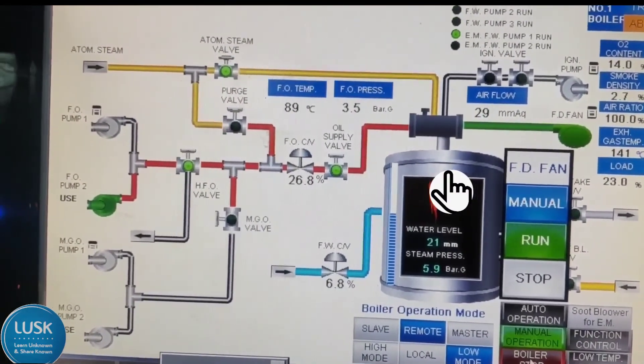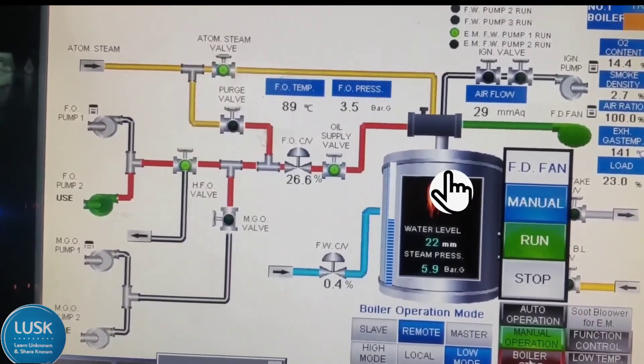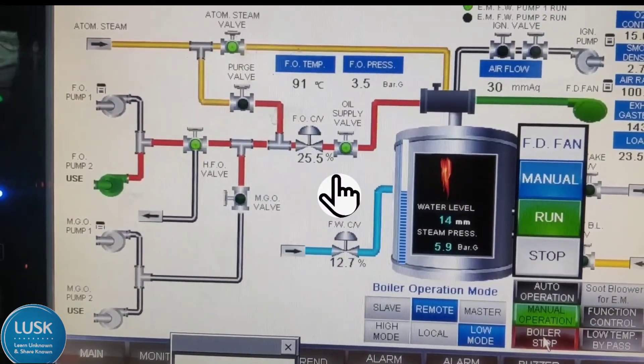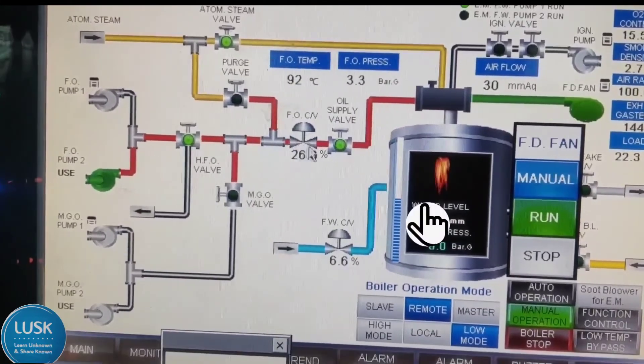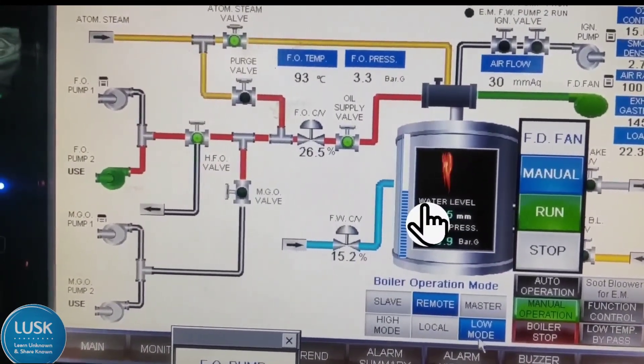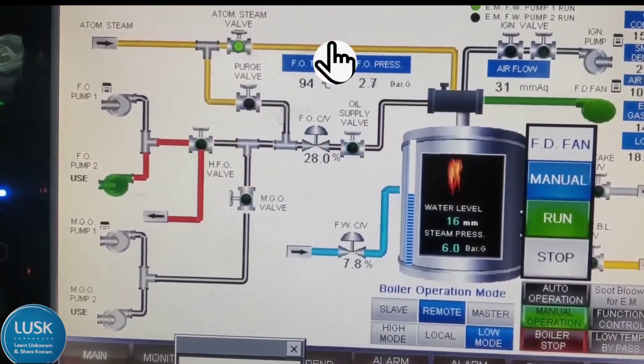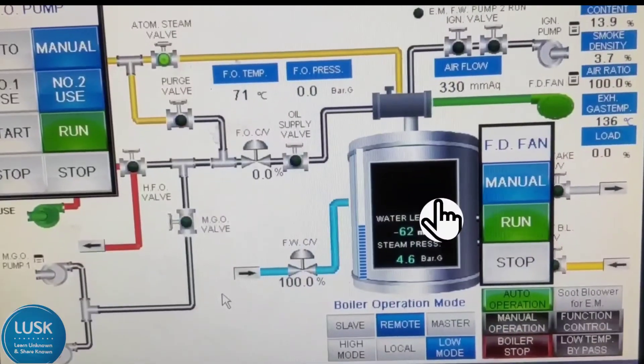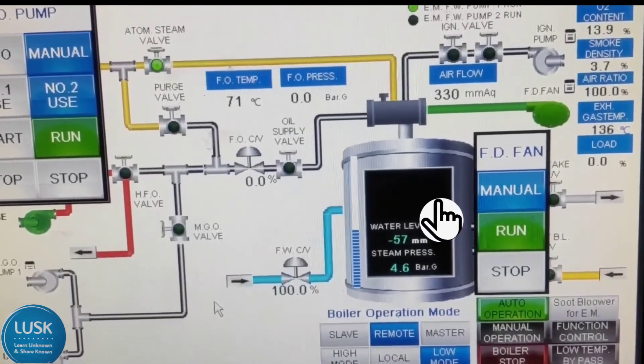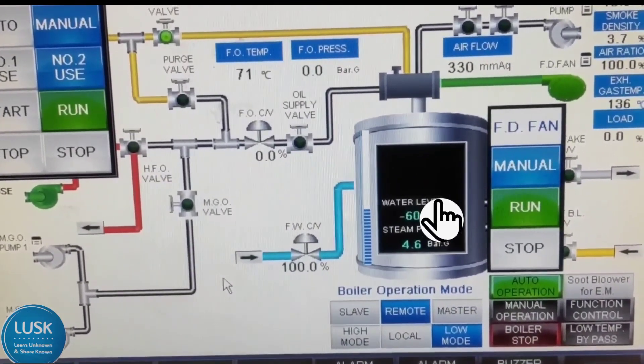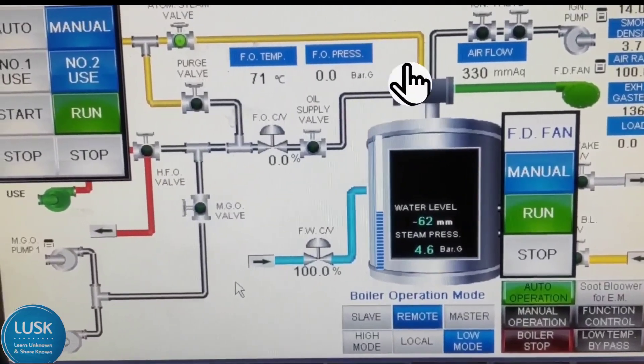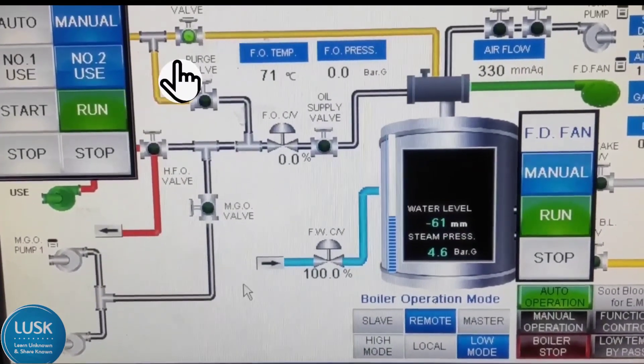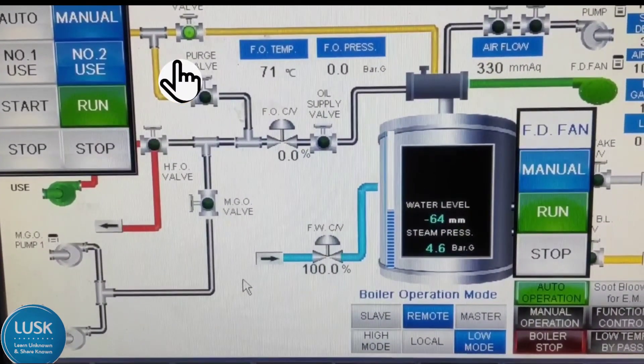When stopping the boiler — when you achieve the required steam pressure in the boiler — the oil valve will close. When there is no fuel, the burner will stop firing. After the burner stops firing, the atomizing steam will go and flush the burner lines to make sure there is no fuel remaining in the lines, for safety purposes. You can see after the stop, everything stopped, but atomizing steam is still going inside. After some time this valve will also get closed. Now the boiler firing sequence is done.